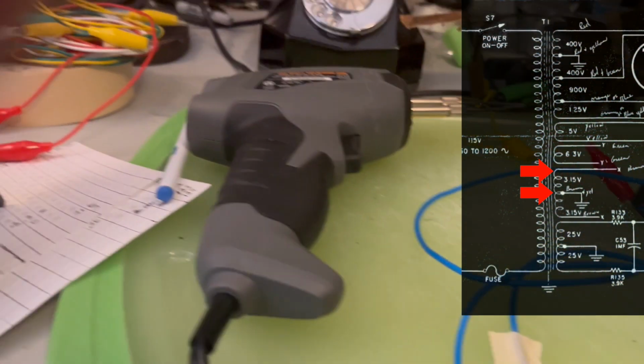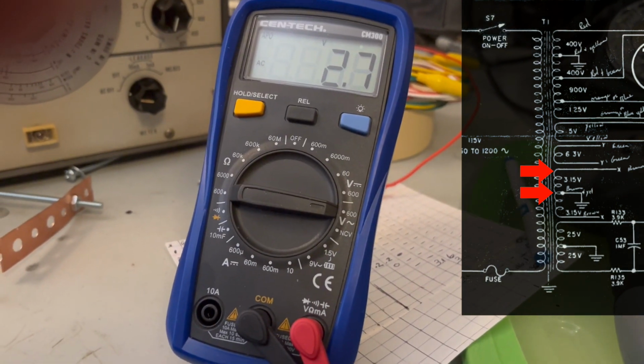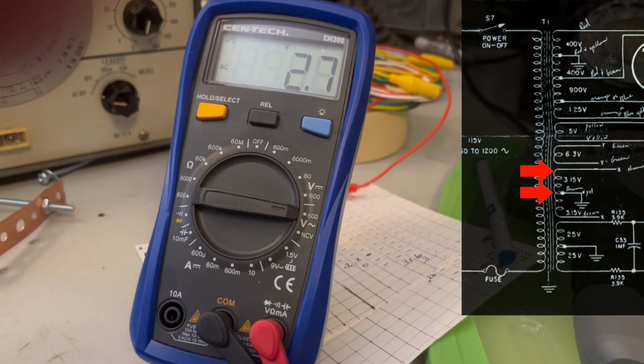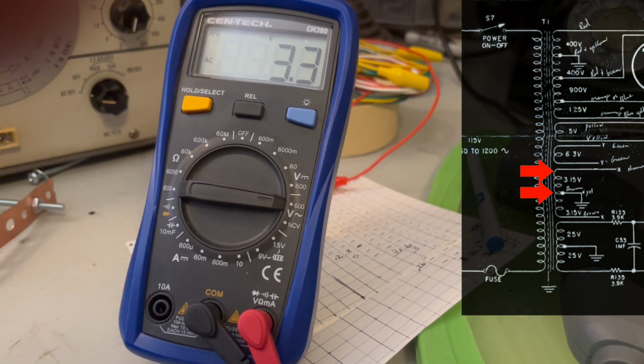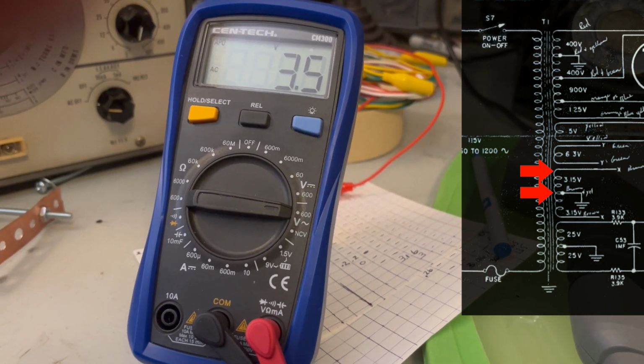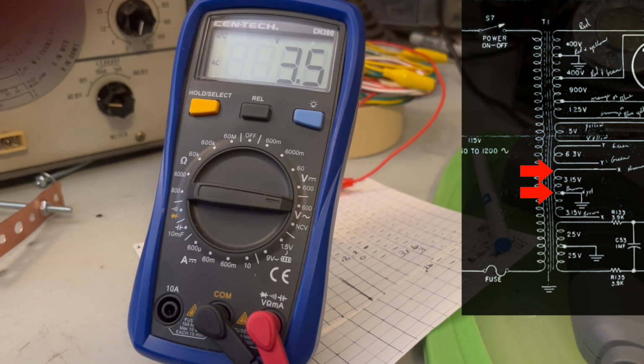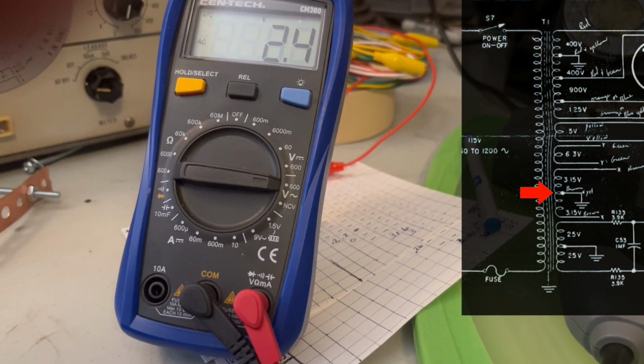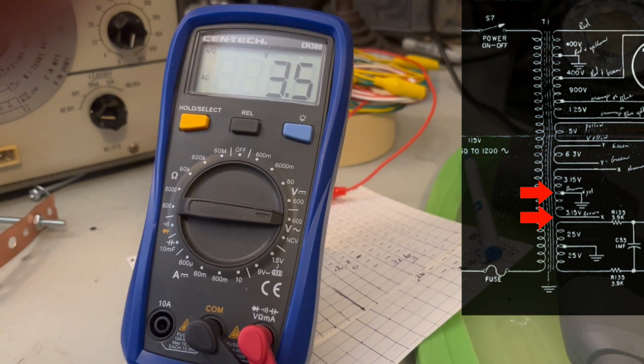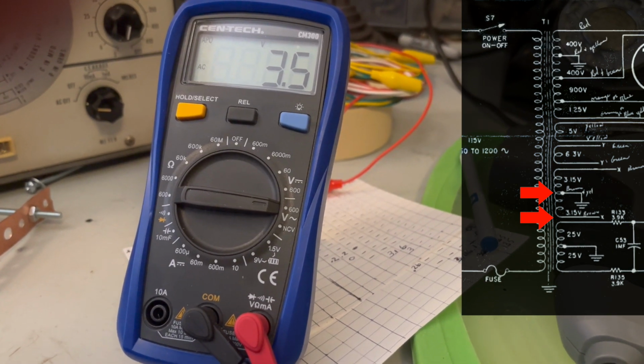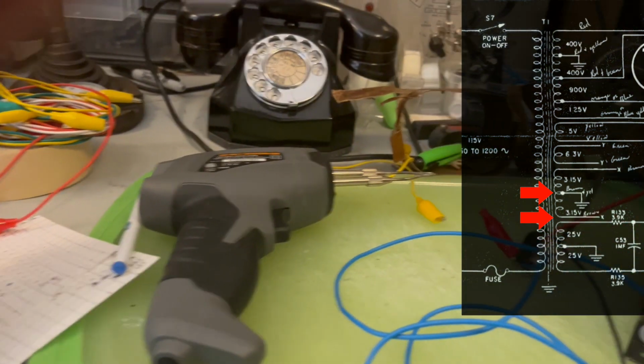This brown coil right here that you're looking at, that was the suspect one. The fact that we're reading voltages right now tells us that it's not shorted, at least. This is reading 3.4, 3.5. It's a little bit higher than what you would expect to see. The other side is also 3.5 volts. That's reading from the center tap, so both of those look good.